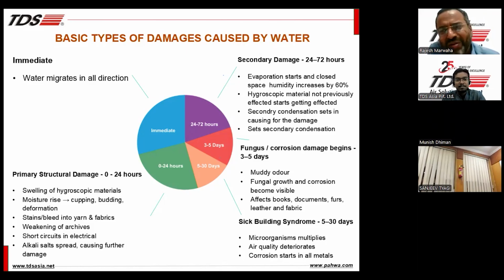Secondary damage occurs after 1, 2 or 3 days, when evaporation starts and humidity increases a lot. It's difficult to work inside confined areas because sometimes there's no power. Condensation starts affecting the damaged equipment, causing secondary problems, especially if equipment is not segregated, since good and bad equipment get mixed together. That takes more time, so it's best to decide within 24 hours to start the restoration process.